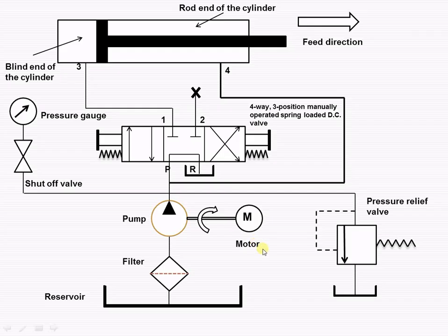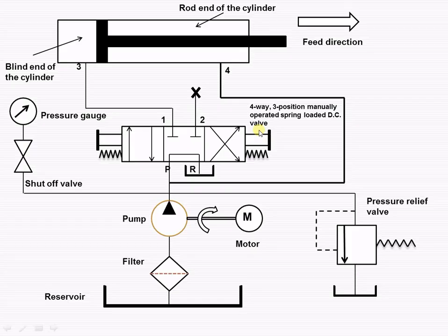Let us try to understand how the hydraulic circuit works. We are taking into consideration the regenerative circuit. The regenerative circuit is used to increase the outstroke speed of the piston of a double acting cylinder. This figure shows a regenerative hydraulic circuit which is used to speed up the operation of the cylinder during its outstroke. It uses a three-position four-way direction control valve with its port blocked, and the lines to both ends of the cylinder are connected in parallel to each other.